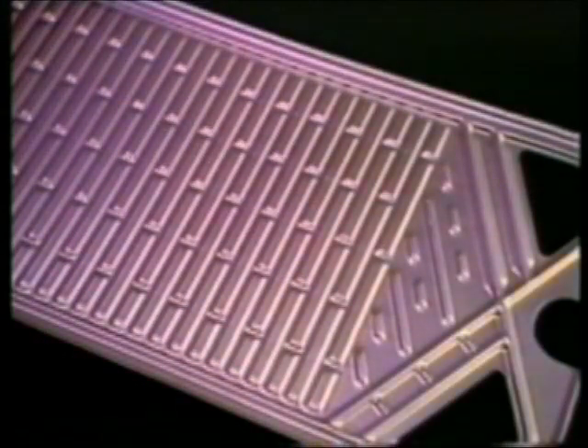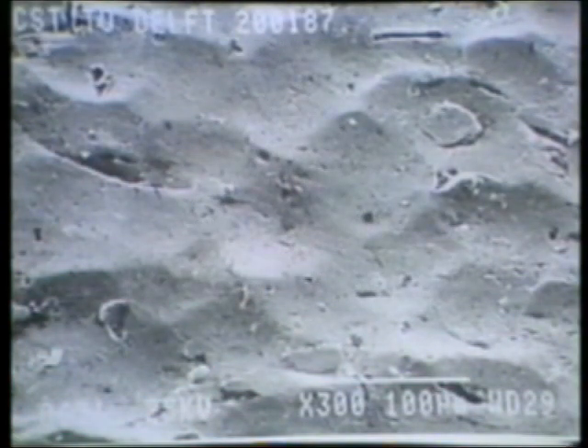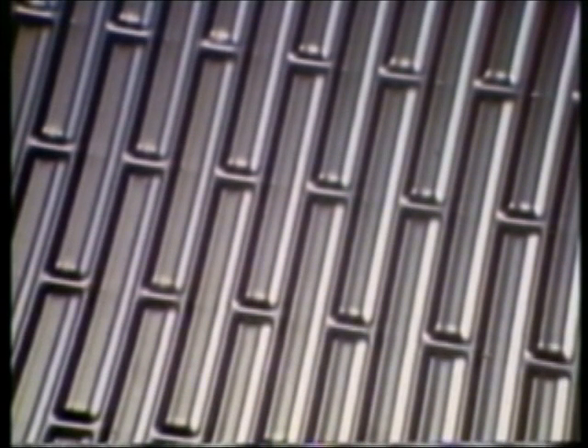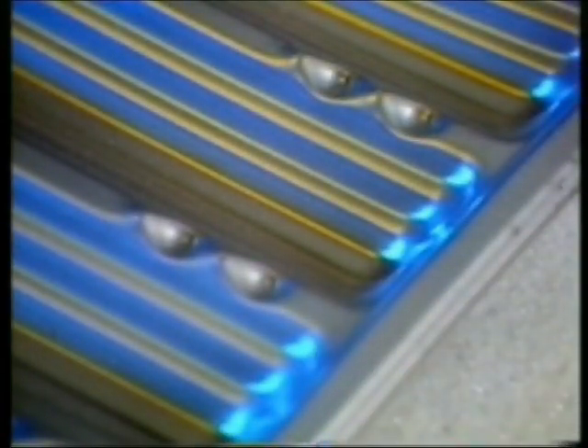Consequently, the result is amazing. Fouling and other deposits are removed during the treatment. By the continuous hammering, the pores are closed up, so the porous surface is transformed into a smooth and undulating surface — at least as observed in the electron microscope. Optically, the surface is completely smooth, insensitive to mechanical adhesion and therefore much better corrosion resistant. The micropeening treatment also builds up a compressive stress in the metal surface, so the risk of stress corrosion diminishes substantially. The hardness of the surface is meanwhile remarkably enhanced.